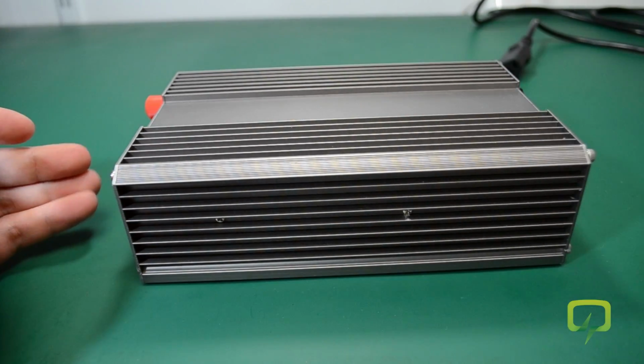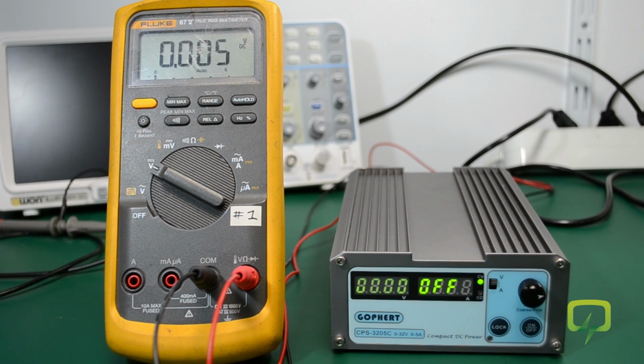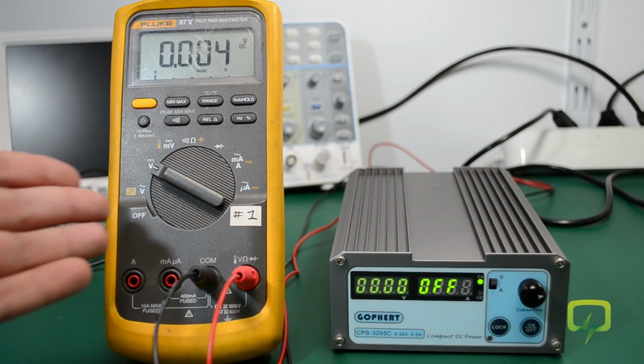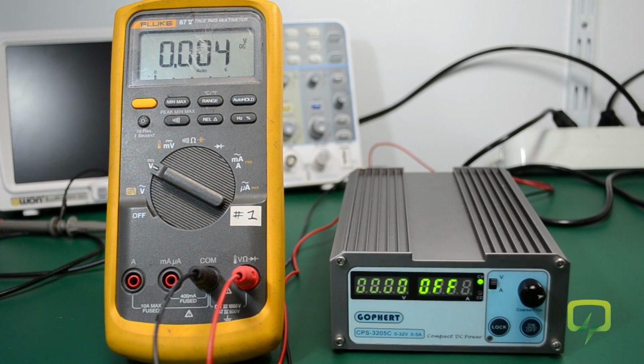For the next part, I'm going to measure some of the specs of this power supply and see what I get compared to its spec sheet. I'm going to start by looking at the accuracy of the voltage and current meter on this power supply, which according to its specs should be better than 0.3% plus 1 digit for the voltmeter and plus 3 digits for the current meter. For comparison, I'm going to use my Fluke 87, which was last calibrated about 2 years ago, so I trust its measurements.